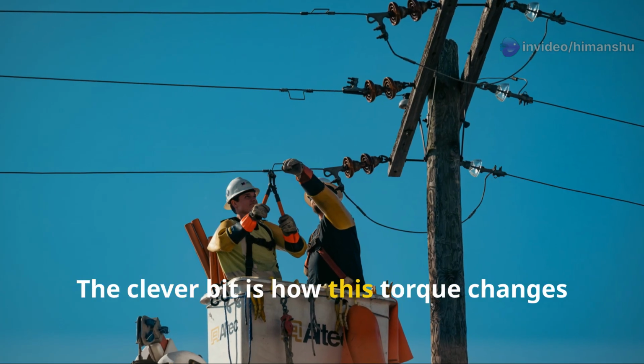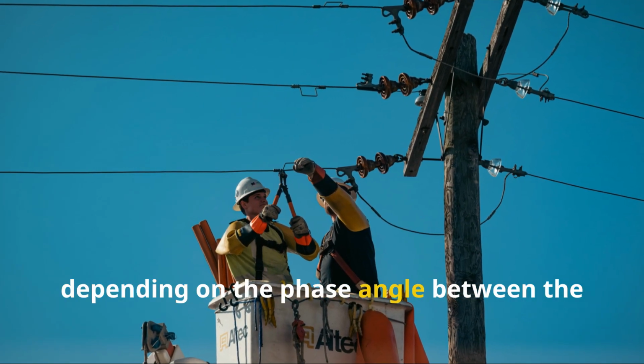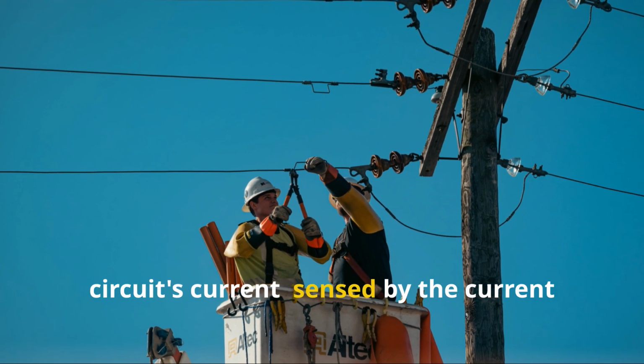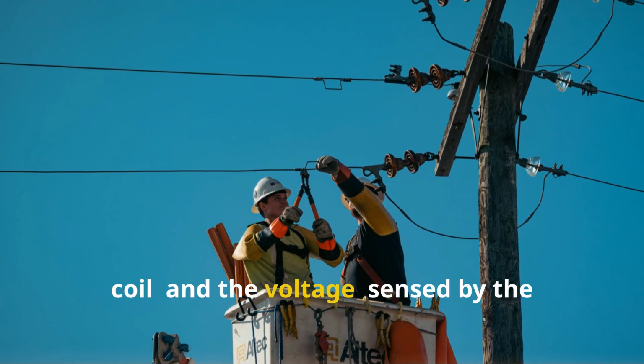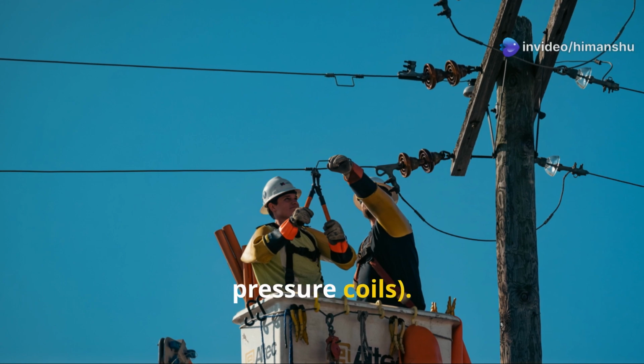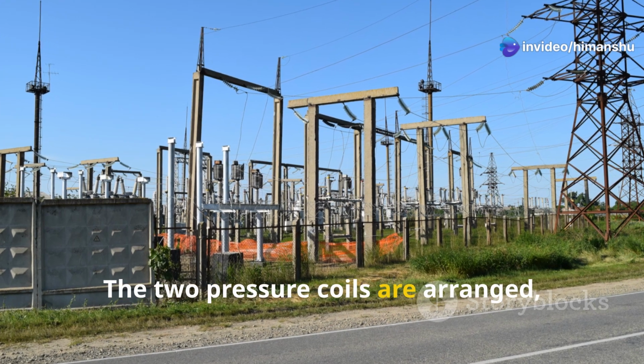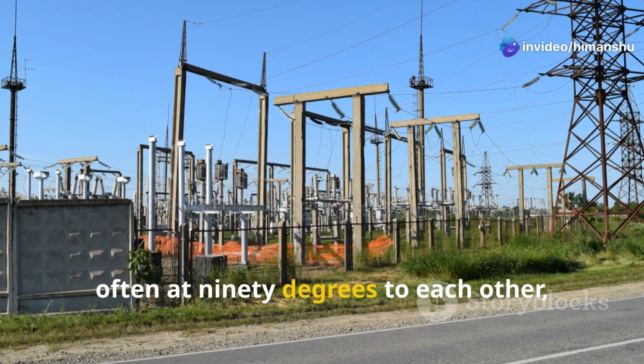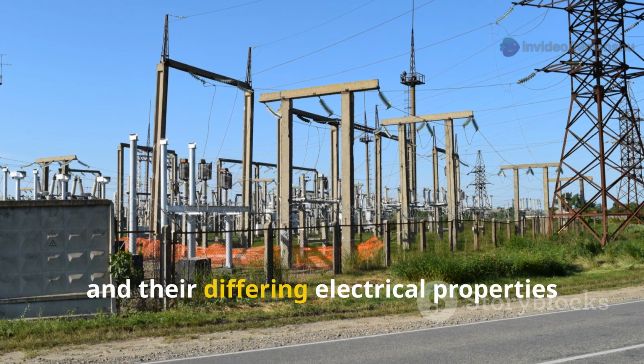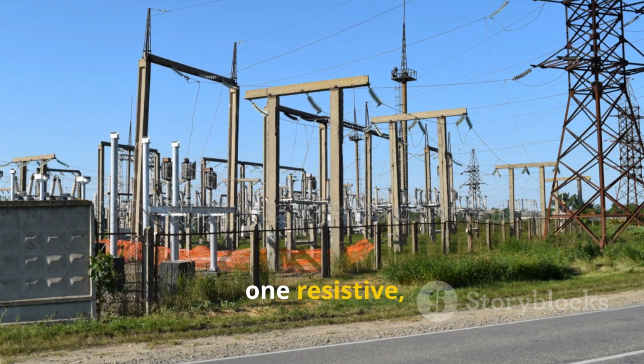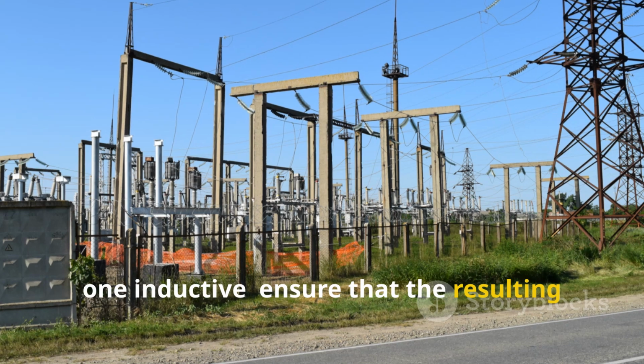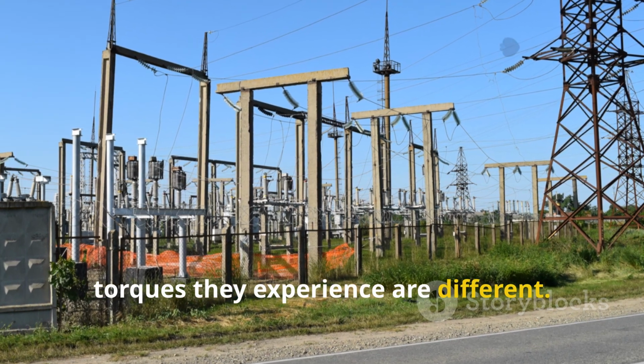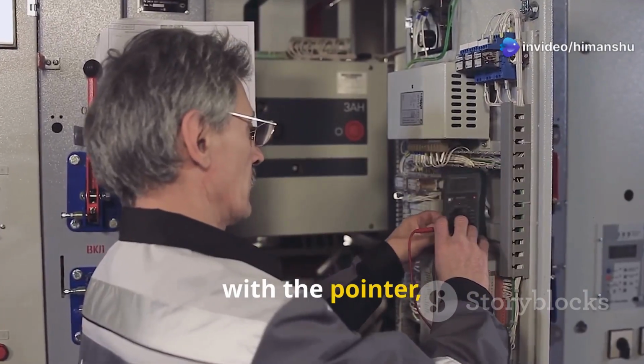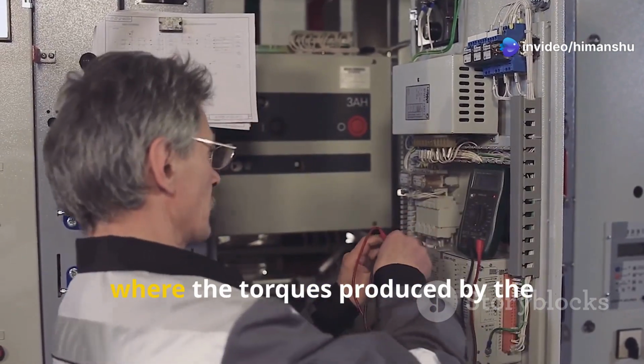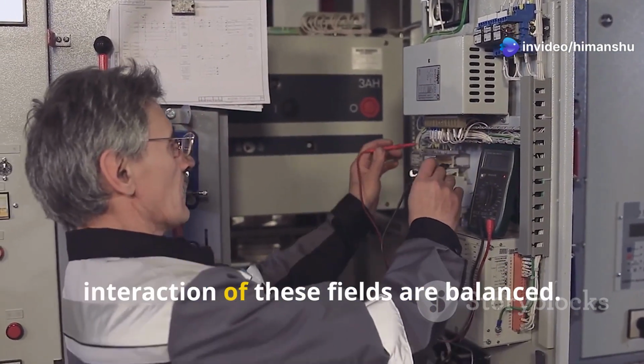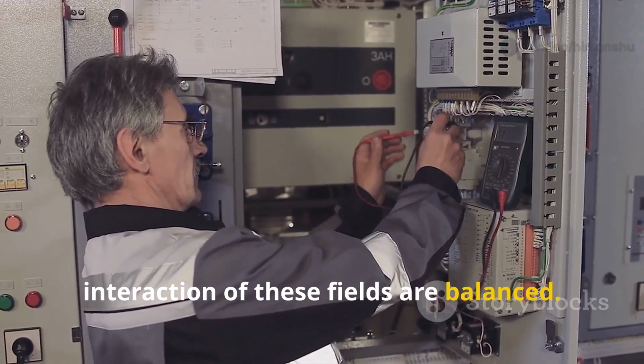The clever bit is how this torque changes depending on the phase angle between the circuit's current, sensed by the current coil, and the voltage, sensed by the pressure coils. The two pressure coils are arranged, often at 90 degrees to each other, and their differing electrical properties, one resistive, one inductive, ensure that the resulting torques they experience are different. The moving system with the pointer will turn until it reaches a position where the torques produced by the interaction of these fields are balanced.